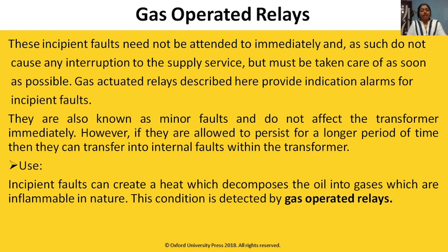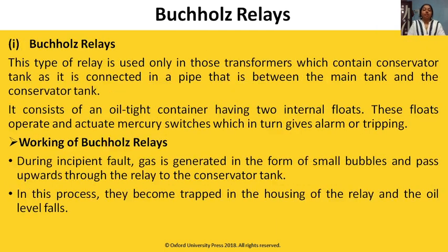Incipient fault can create a heat which decomposes the oil into gases which are inflammable in nature. This condition is detected by gas operated relay. Now when you visit the substation, or when you visited the substation, you can see there is a Buchholz relay. Pressure relays, sudden pressure relays are there. So these relays are used for incipient faults. These relays detect and clear the fault.